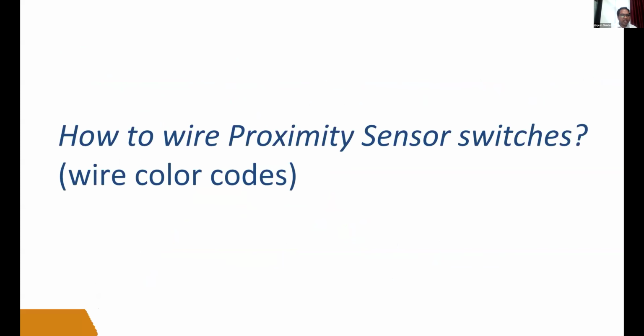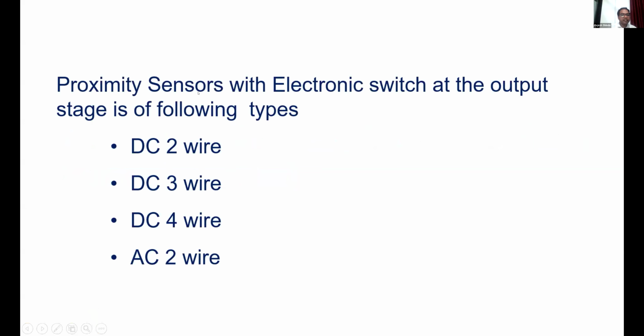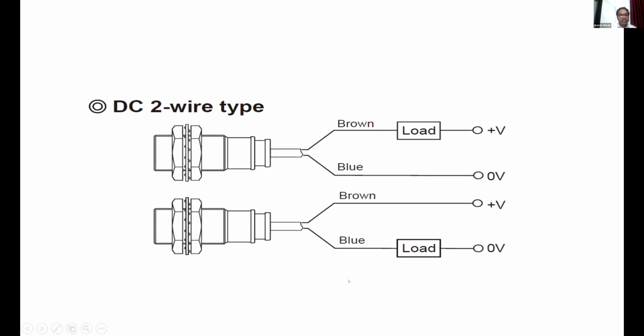Yes. Now, for the next example, I have taken the proximity sensor. As I already told you, for pressure, temperature and humidity, the working principle and the wiring are the same for all sensors. I have shown it in the next diagram. Now, I have taken the example of the proximity sensor. We can see there are various types of proximity sensors: DC 2 wire, DC 3 wire, DC 4 wire, AC 2 wire. Now see here, if you are using the DC 2 wire sensor, you will connect the output. Actually, the color code is very important while using the sensor.